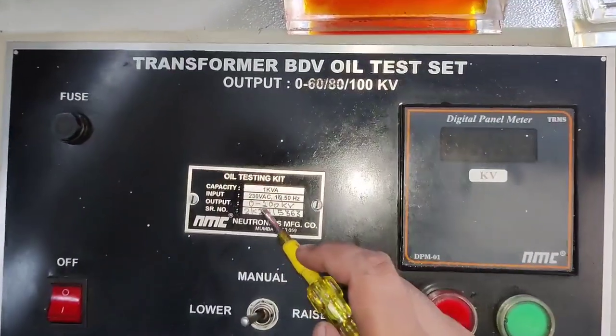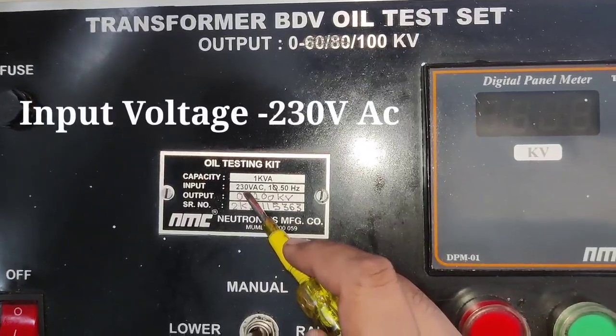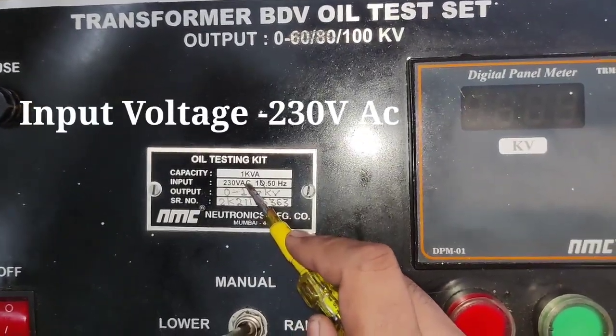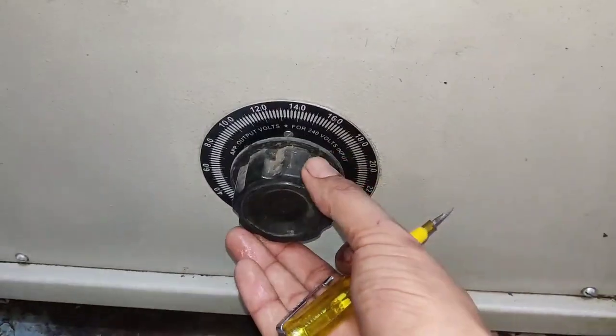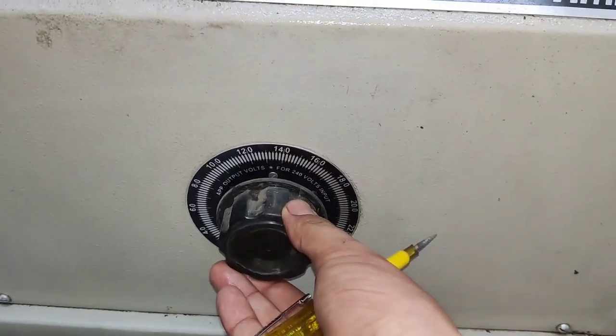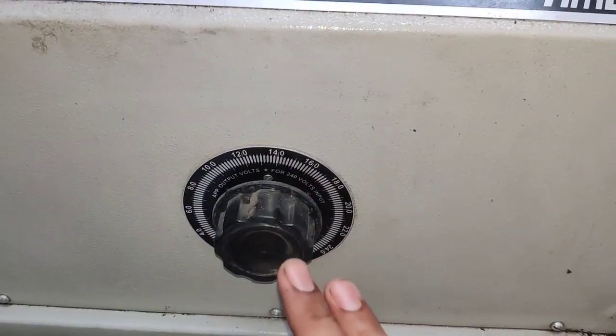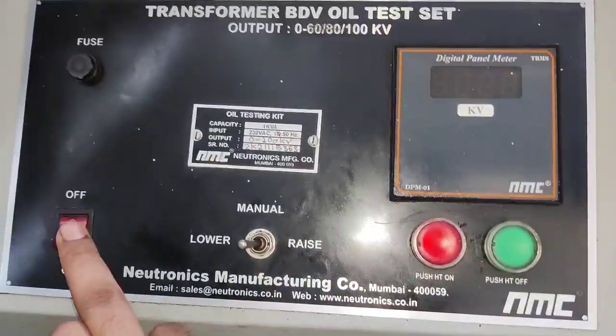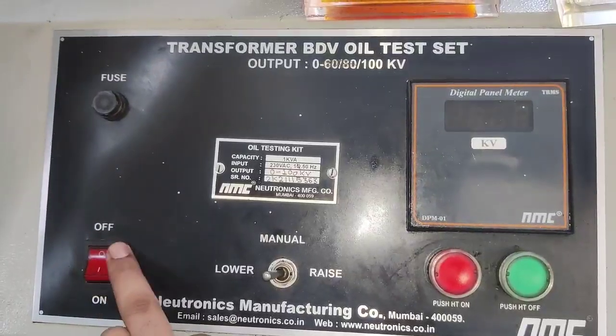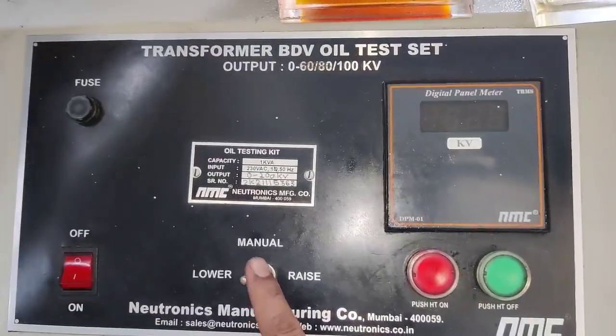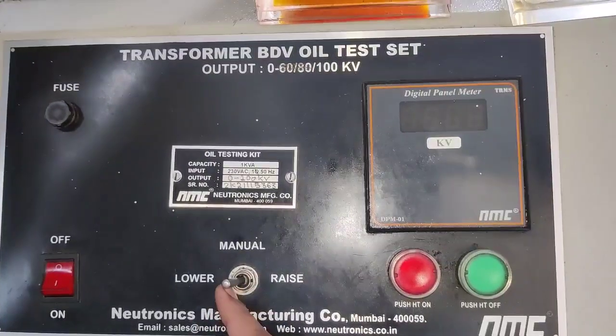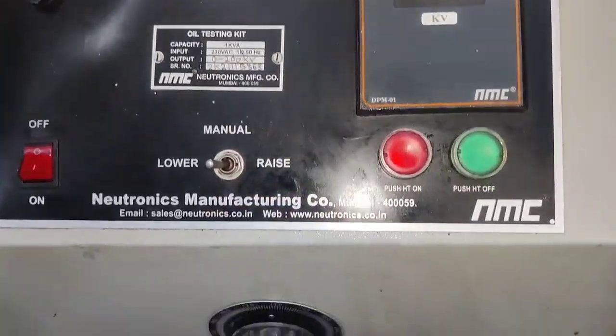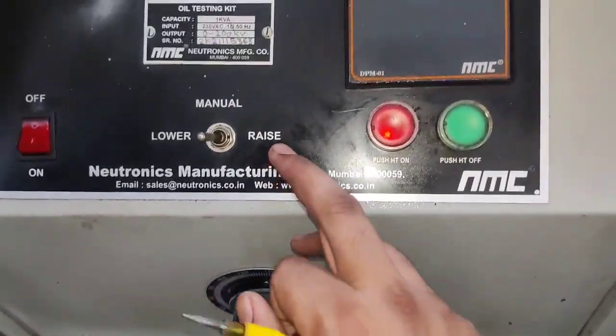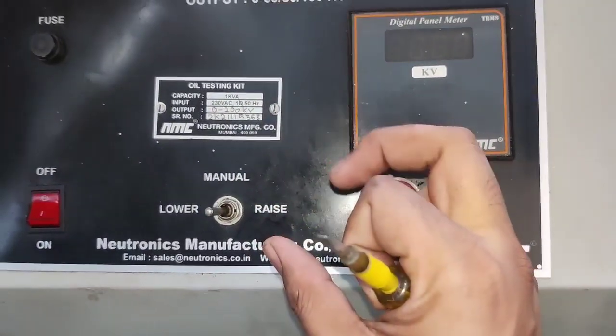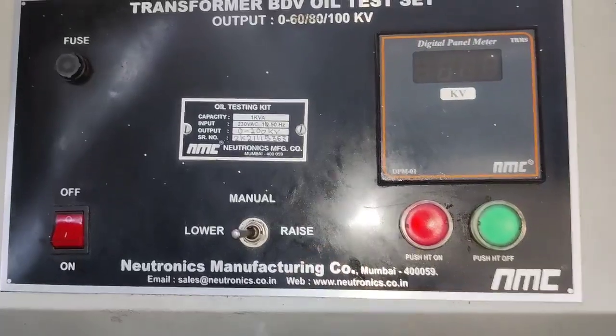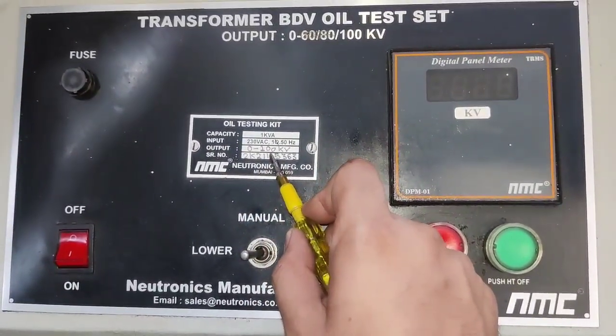In this kit, the input voltage is 230 volt AC and the output voltage is 100 kilovolt, which is very high voltage. For the input voltage, we have one variac. By this variac, you can vary the input voltage from 0 to 230 volt AC. This is the start-stop button of the machine, and we also have one manual or auto switch. If you set it in the lower position, you have to vary the input voltage by the variac, and if you set it to rise, then the voltage will increase automatically. That means the machine will run in auto position.